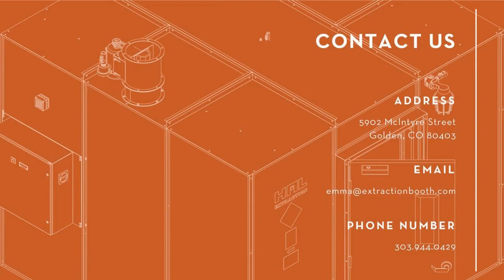Most of our customers are off-gassing within the current room, but that poses a bit of an issue, because if you're off-gassing a lot of biomass that still has some residual solvent in it, it will crank up the lower explosive limit in the room. So we're currently in the development phase of making an off-gassing room that will connect directly to the Halo room, and then you can just put biomass in there, and it has a dedicated fan and sensor, and you can off-gas that in a separate space, so you're not adding more flammable solvent to a working environment. And that should be available within a few months.